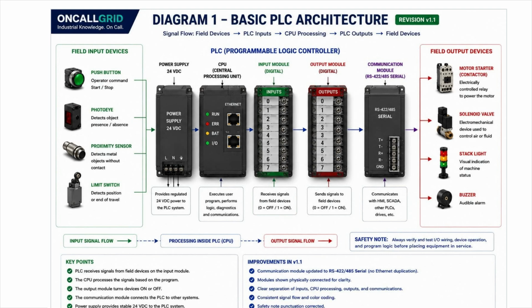Then the input module, digital inputs. This is where your field devices, push buttons, sensors, switches, plug in. 0 means off, 1 means on. Simple as that. Right after it, the output module. Same idea, but sending signals back out to the field. 0 off, 1 on. And last, the communication module. On this one, it's RS422/485 serial, a separate physical link used for things like drives or point-to-point serial connections. That's different from the Ethernet on the CPU. Don't mix those two up. They're two separate communication paths doing two separate jobs.